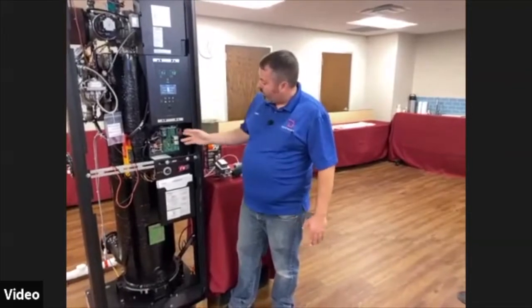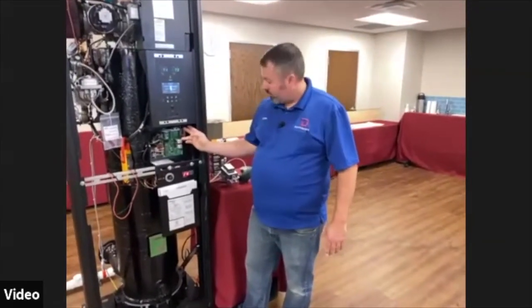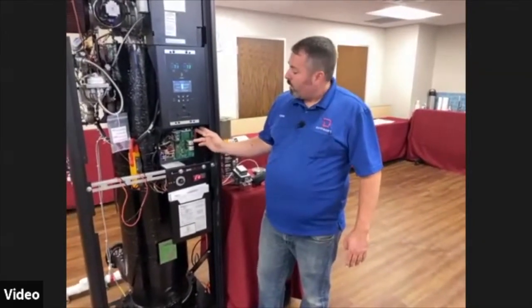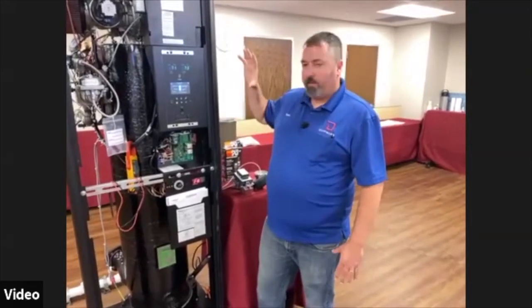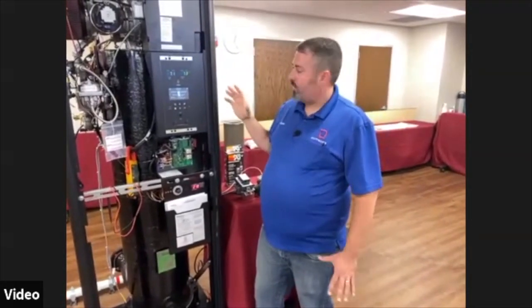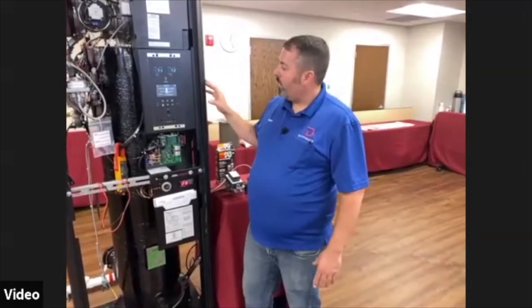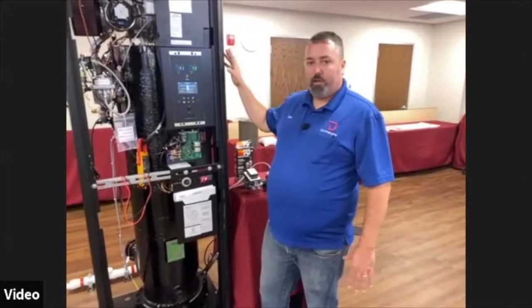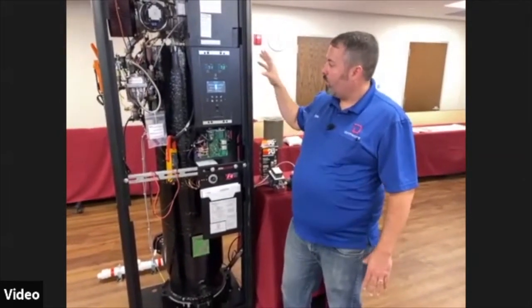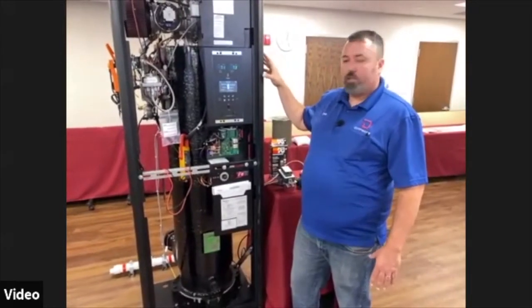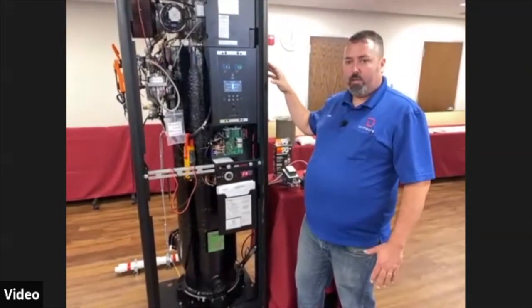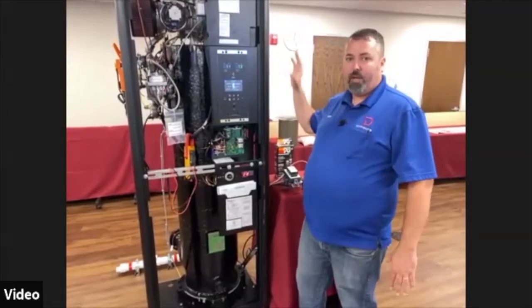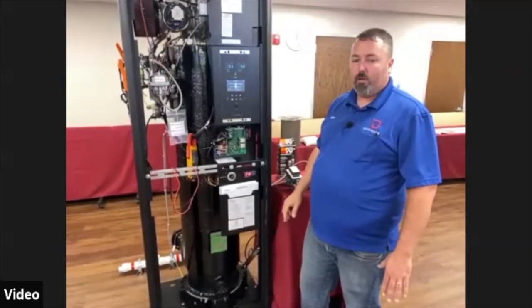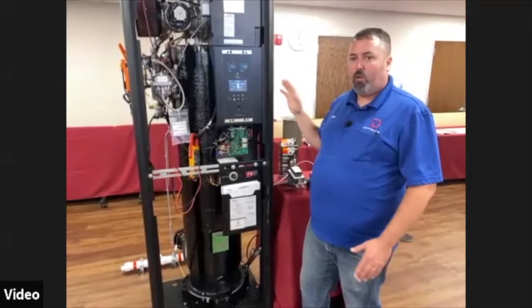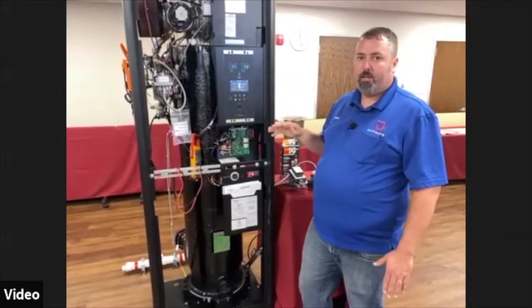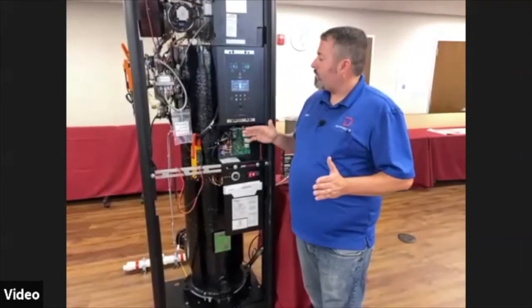What it's going to do is once we are enabled from our building automation, which is where the green jumper would be, once that's enabled and the system has a call for heat depending on set point and how that's all set up, whatever boiler is determined to be the lead boiler will fire. The first thing that it will do is go through an auxiliary start delay if you have the isolation relay installed. With that isolation relay, you'll put in a 120-second delay, and it'll go through that 2-minute timer.